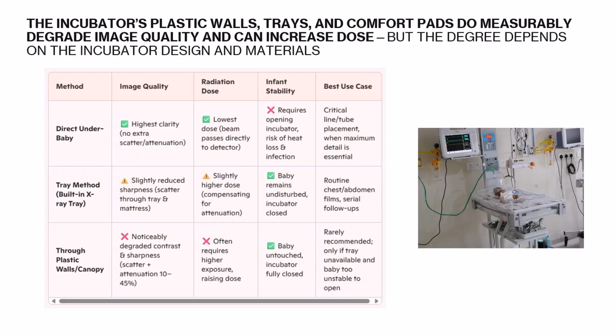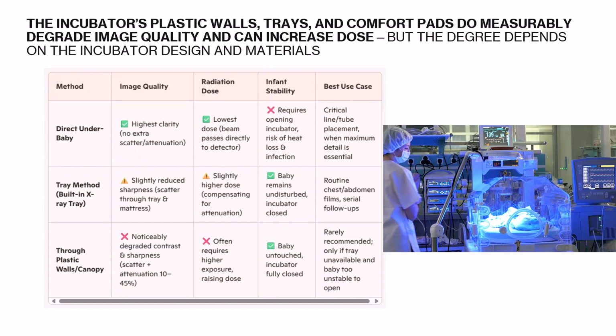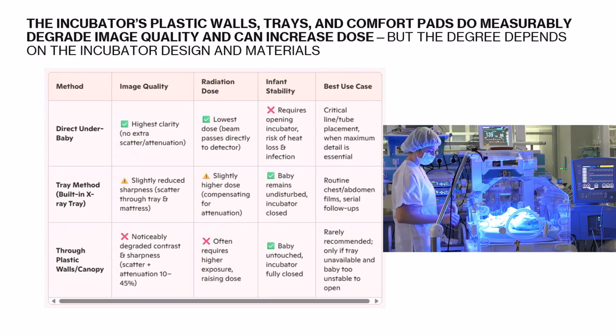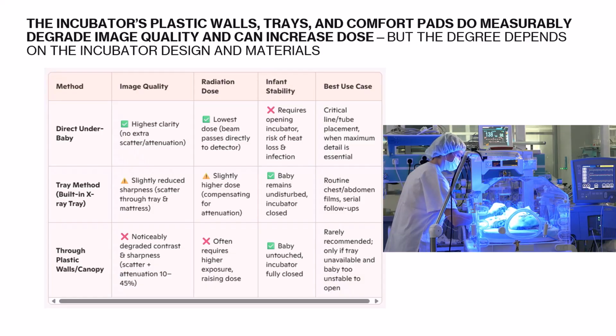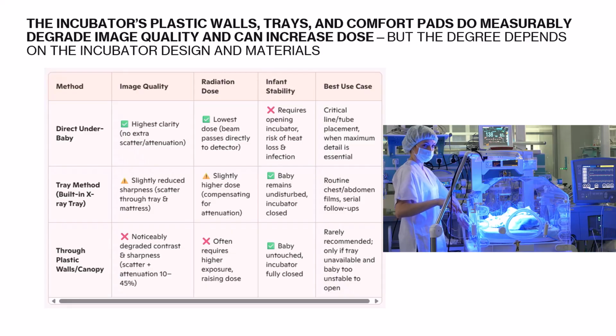If tray use is unavoidable, the best practice is to slightly increase your mAs and increase your distance, your SID, to balance dose and clarity. Comfort pads and tray plastics can attenuate the beam by 6 to 15%, usually the exposure at 60 kVp, depending on the materials, of course. Thicker, denser trays, some are even thicker than usual, can attenuate up to 45% of the dose.